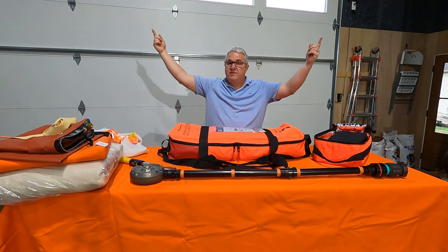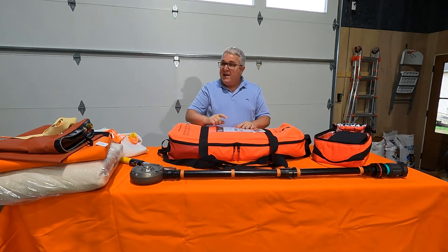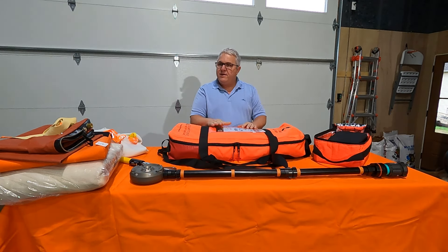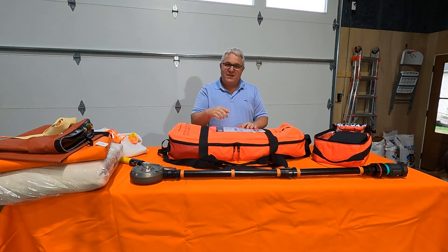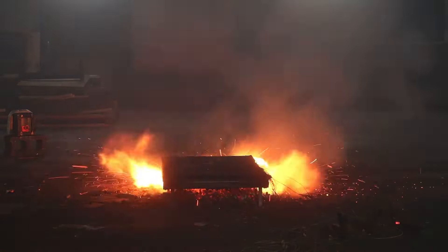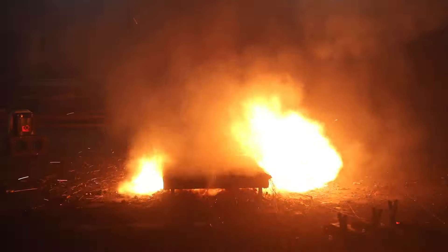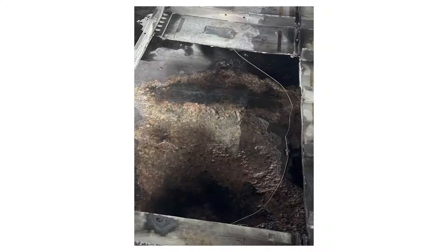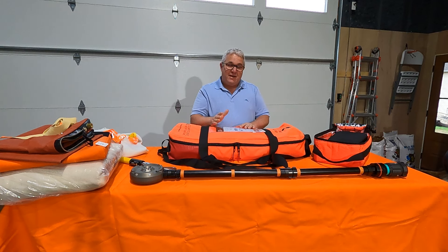Batteries were hitting 35 feet up in this facility because they were exploding. We call them 'spinners' because they look like 4th of July firework spinners — we had them zinging all over the place. I encourage you to watch the video on our training and resources page. There were so many jet flames bursting out of the bottom that we actually ruined the concrete in the facility — put about an inch to inch-and-a-half pit into his concrete. It is a different monster when you allow free oxygen.